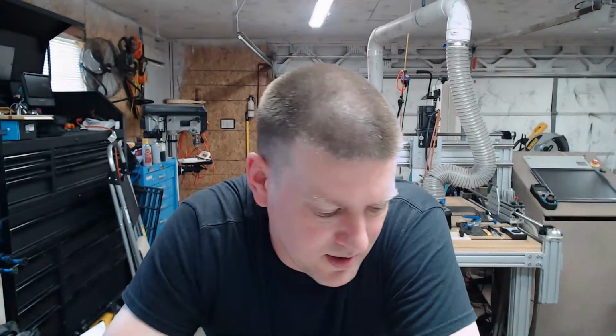There are different isolation power systems, a bunch of different ones, but I'll tell you right now, it's one humongous, beautiful transformer down the bottom of the cabinet. There's no chopper drivers or anything like that, no rectification whatsoever. It's primaries in at probably 400 volts or so, and then your secondary outs - it has to be a step down transformer. The mains coming into that transformer are massive, and the secondaries coming out going to your fuse panel are a bit smaller.